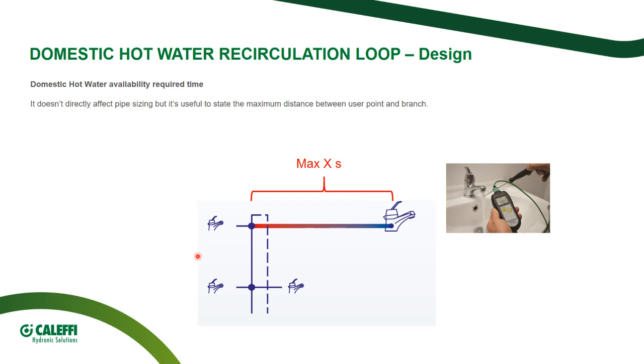On the other hand, as we stated before, it was one of our targets, we also have to comply with certain standards according to which my domestic hot water shall be available within a certain period of time from the moment I open the tap. This is also related to pipe length. So when we are requested to design, for instance, a 5-star hotel or a hospital where people cannot wait so much time to have hot water, I cannot put the recirculation loop connection and the tap too far apart. That's why it is better for the recirculation loop to be as capillary as possible.